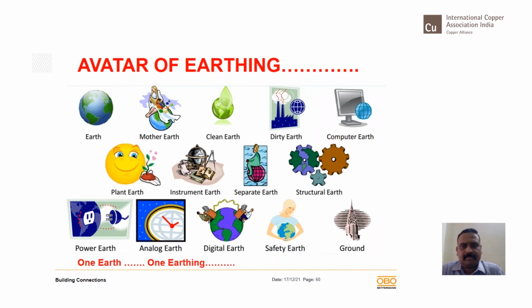And remember, in India, earthing has taken more avatars than Mahavishnu. Everybody says a different name for earthing: Mother Earth, Dirty Earth, Computer Earth, Instrument Earth, and many names are being given. However, remember, when it comes to earthing, there is only one earth which is in common, and that earth is sufficient for you to interconnect every equipment. Otherwise, the earth automatically gets interconnected.